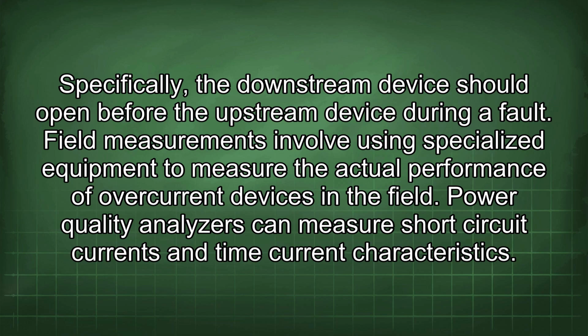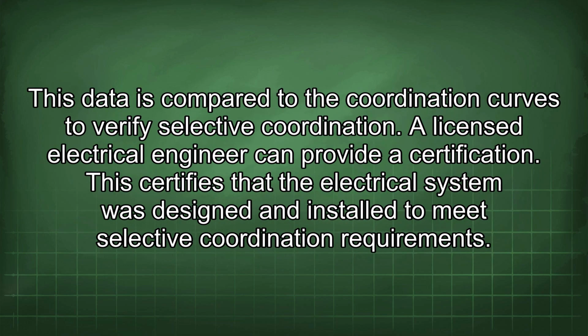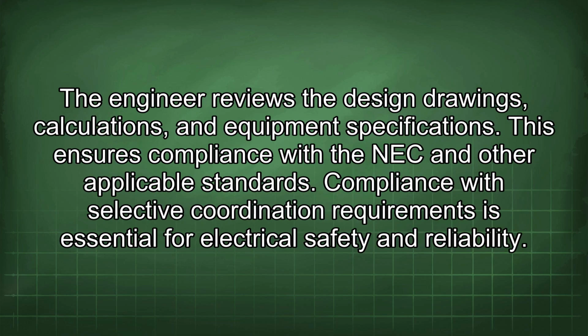Field measurements involve using specialized equipment to measure the actual performance of overcurrent devices in the field. Power quality analyzers can measure short-circuit currents and time current characteristics. This data is compared to the coordination curves to verify selective coordination. A licensed electrical engineer can provide a certification. This certifies that the electrical system was designed and installed to meet selective coordination requirements. The engineer reviews the design drawings, calculations, and equipment specifications. This ensures compliance with the NEC and other applicable standards.